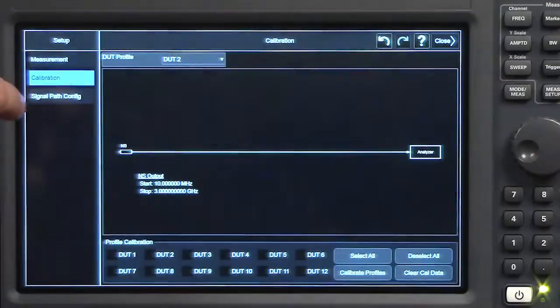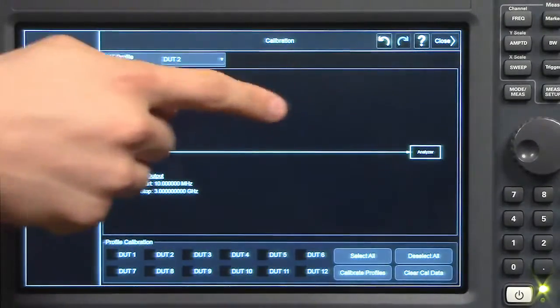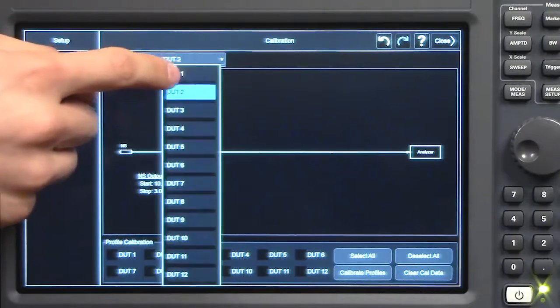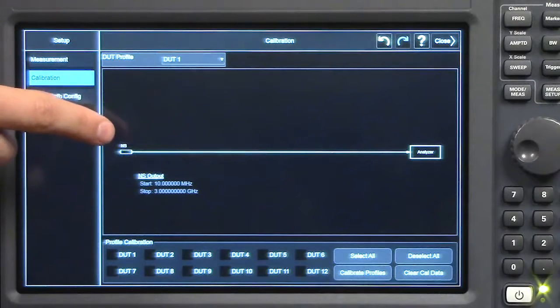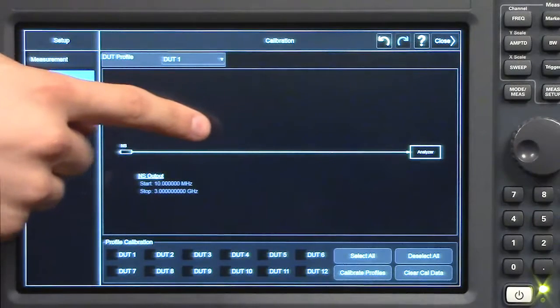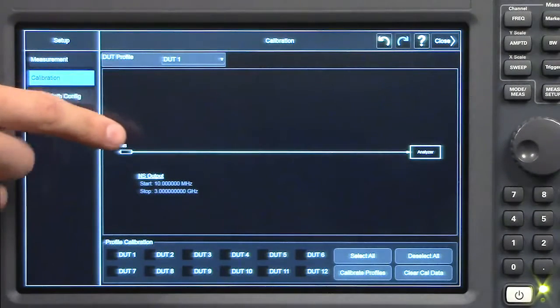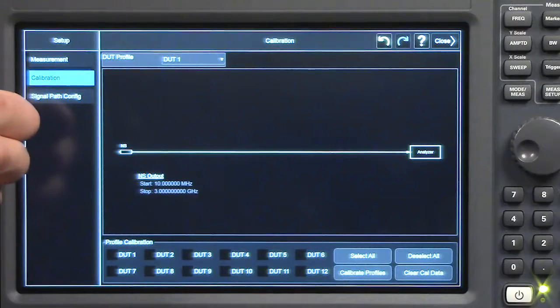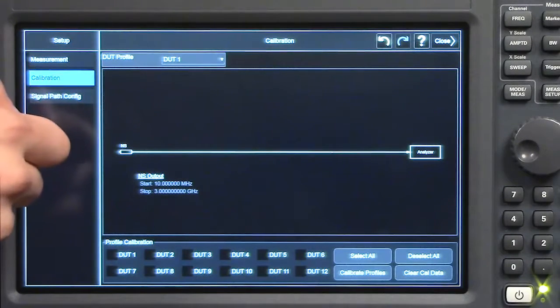Next, let's go to the calibration tab, where we can see the calibration setup required for the selected DUT. Both DUT1 and DUT2 just have the noise source connected directly to the analyzer because I do not have a system down converter or external preamp involved.